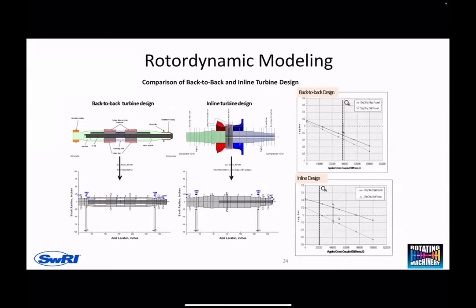However, due to the rotor dynamic concerns and increased cooling, it was actually detrimental to our design. So we ended up going with a straight-through turbine design, similar to what you'd have on gas turbines versus steam turbines, where you see a lot of back-to-back designs.